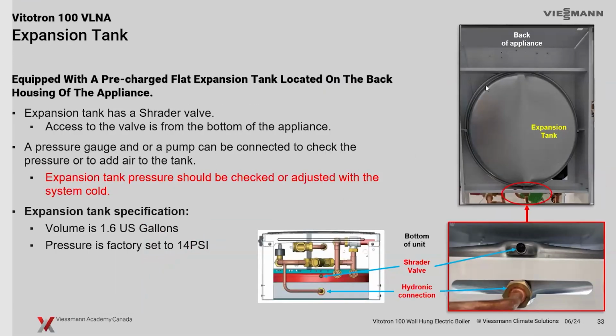On top of that, as I mentioned, we have a little pancake style expansion tank that's sitting in the back. We've got a little Schrader valve there that you can access for service should you need to, but it sits at the back of the unit here. Reliable little expansion tank. We've had these installed now for a number of years. We haven't had any issues really with these expansion tanks. They are 1.6 gallons. They're set for 14 psi. Remember, your minimum pressure is about 7 psi. System pressure is typically about 3 psi higher than your expansion tank pressure, just to put a little bit of a water seal on that expansion tank. So your typical pressure here with that set at 14 would be somewhere around 17 psi. So well above the requirement of the minimum 7 psi that we have in the pressure sensor.